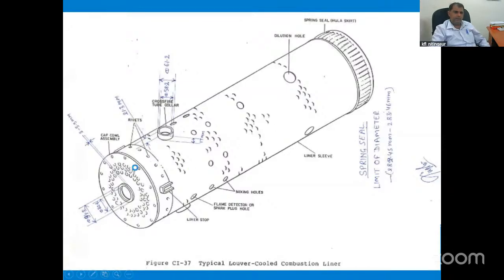This is the combustion liner. Inside this, combustion takes place. At the time of combustion, the temperature of this area is very high, so the metallurgy of these parts is very important. All the parts which are in contact with high temperature are made of nickel and cobalt based alloy, high nickel and high cobalt, approximately 39% cobalt and nickel. It has a special metallurgy name, GTD-111. Very special material is there.